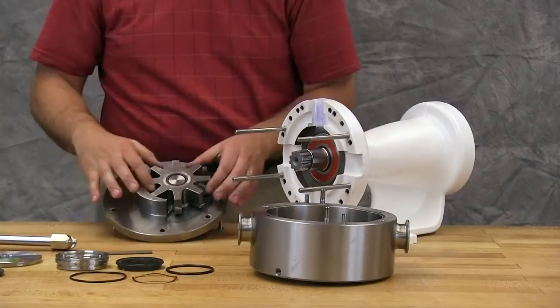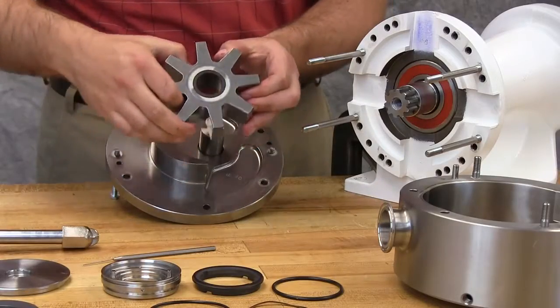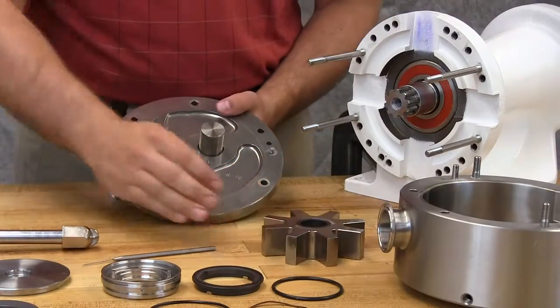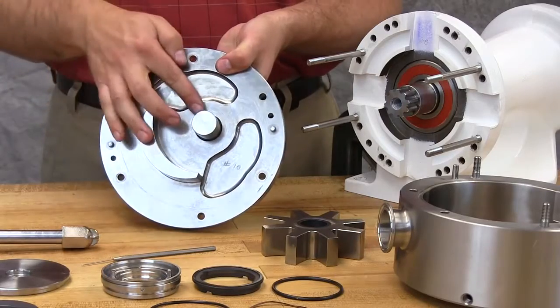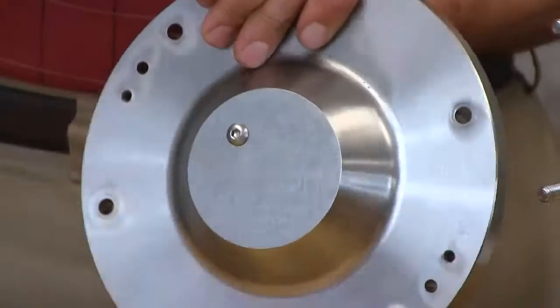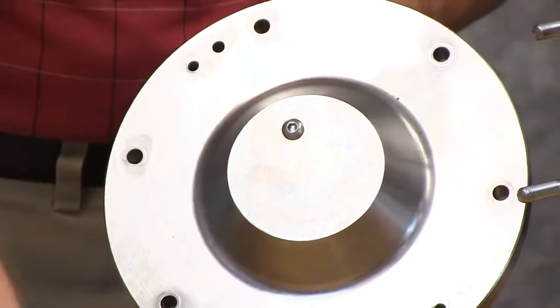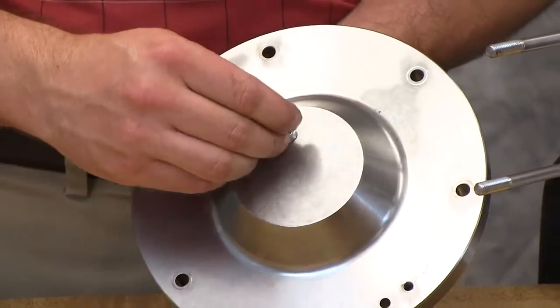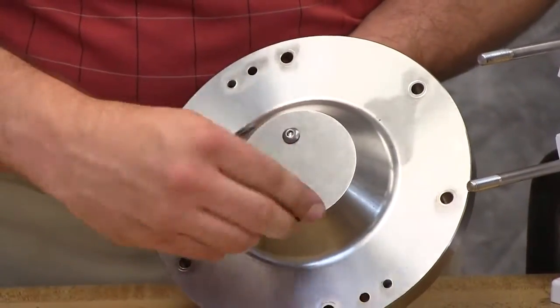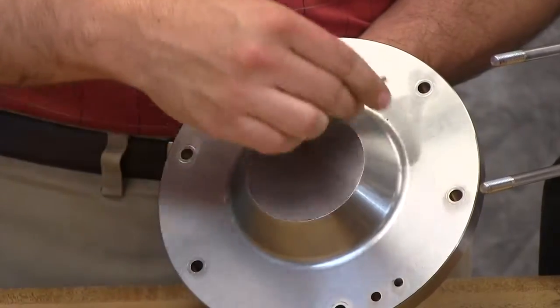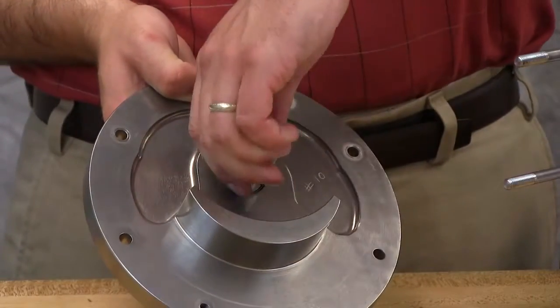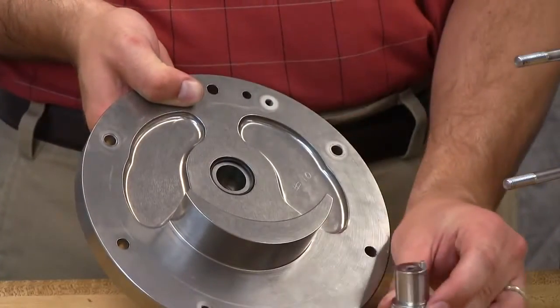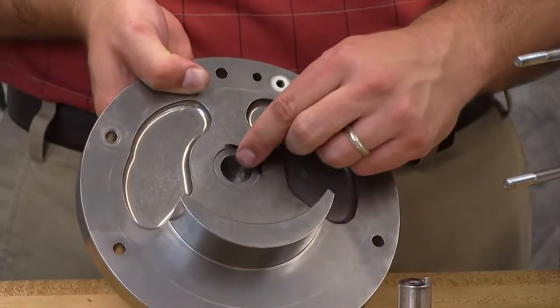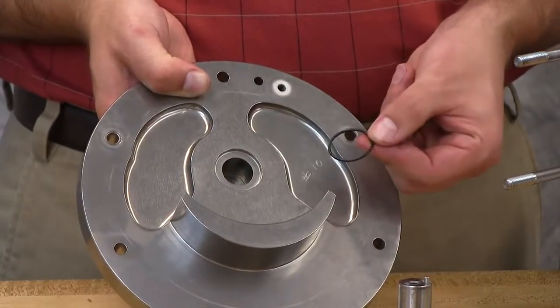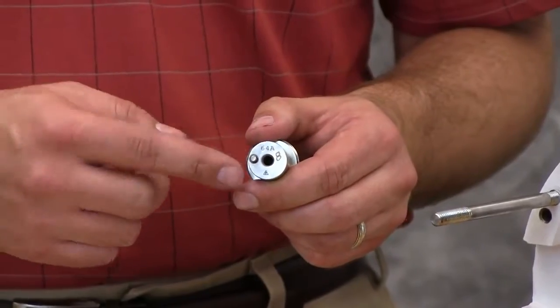Remove the idler assembly from the idler pin. The idler pin does not need to be removed from the head unless the O-ring material of the pump is not compatible with the cleaning solution. To remove the idler pin, remove the idler pin cap screw. Then remove the idler pin O-ring, and idler pin dowel pin.